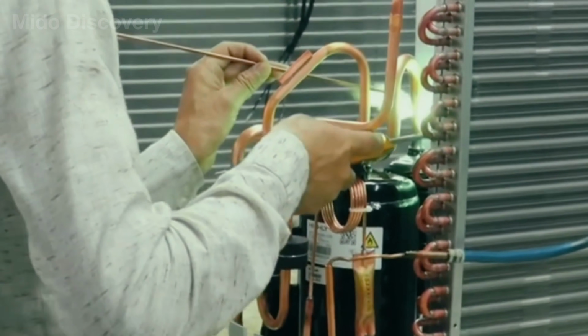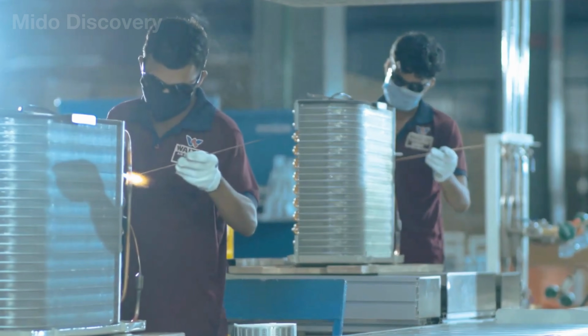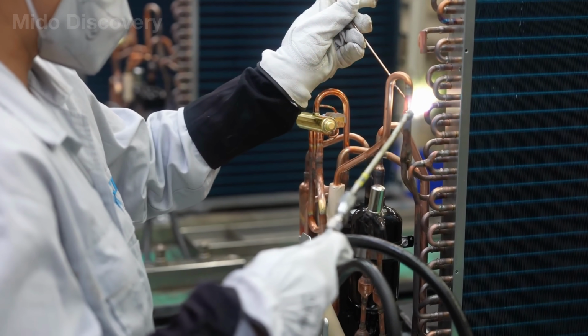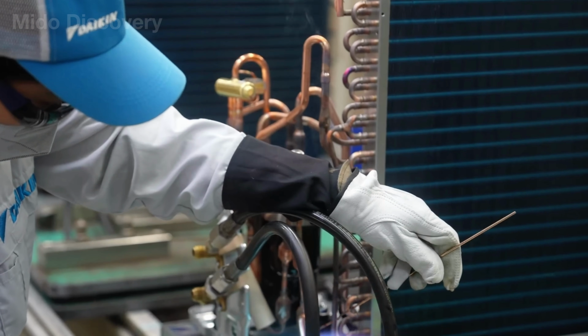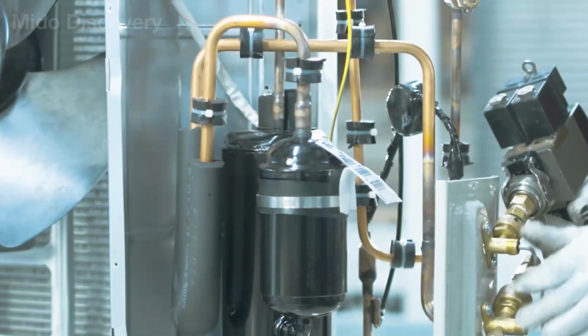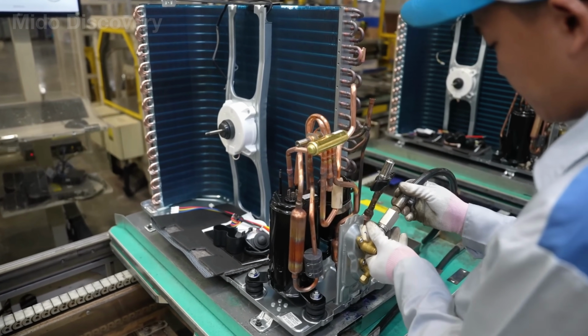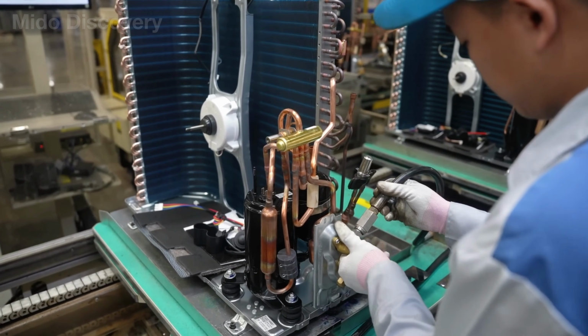But why is the component responsible for cooling placed outside the room? Because the compressor does not directly produce cold air. Instead, it compresses and drives the refrigerant through the system, carrying heat from indoors to the outside.